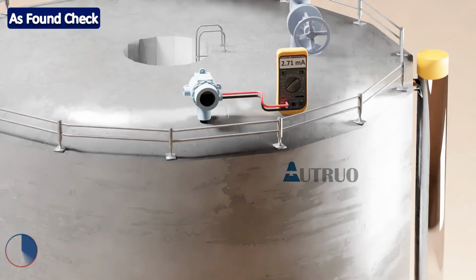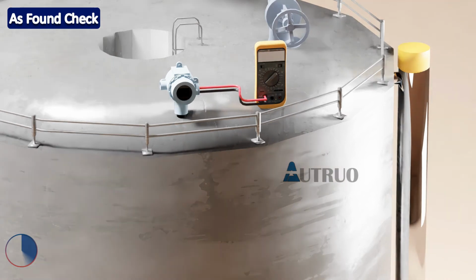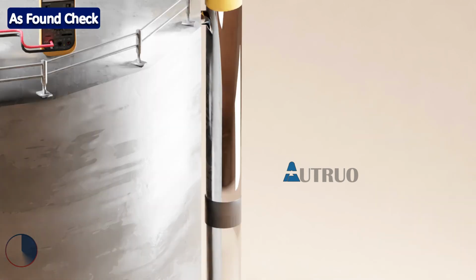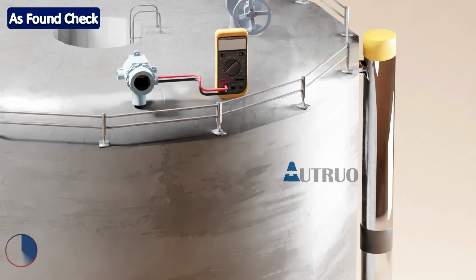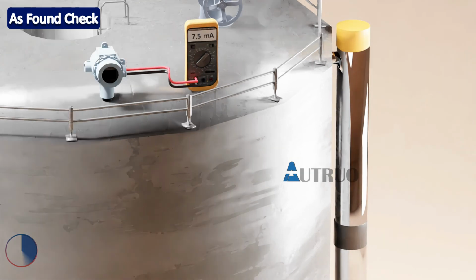The current gotten is 2.71 milliamps. This value is unacceptable. We will fill the tank to 50% of its capacity. We will look at our multimeter again. The current gotten is 7.5 milliamps.